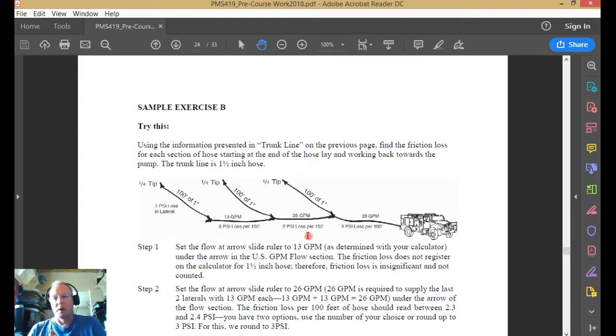Now, another problem that I've seen is people will sit here and go, oh, well, I've got 13 gallons a minute. And they'll assume that the gallons per minute is the nozzle pressure. You've got two different numbers here. A third problem that I've seen is that people will start adding nozzle pressures. You count one nozzle. Not all three, not two, just one in a progressive hose lay. So 50 PSI is counted once, but you sum all of the nozzles to get the total flow required that the pump has to push from the engine up to the first wye.